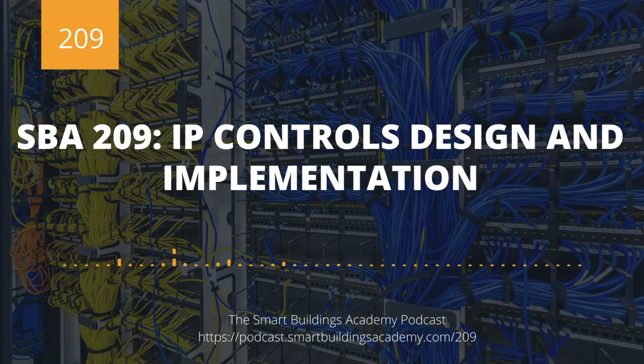I'm not really going to get into that in this episode. It is something we will cover in our upcoming live class. The important thing to understand is that when you're dealing with any of these architectures, they all have their pros and cons. Ring is going to use more wire than bus, but less wire than star, and it's definitely going to use fewer ports. But it's going to be a little more difficult to set up with rapid spanning tree protocol. Bus is pretty easy to set up, but it's the least stable in that if you lose any controller on that run, you are going to lose all the controllers after it.